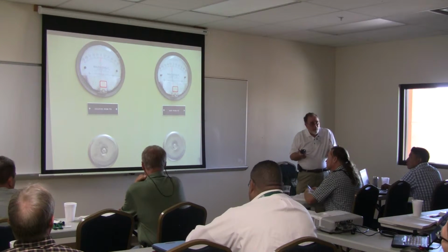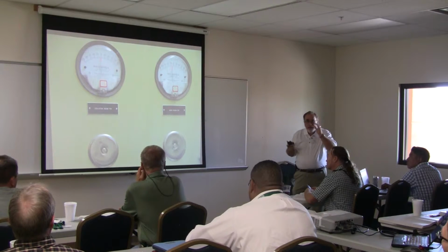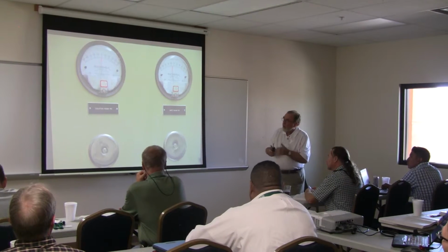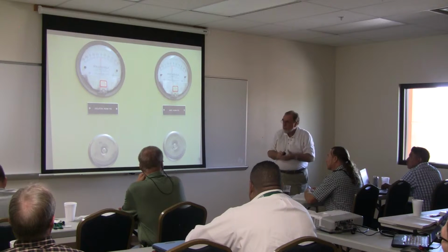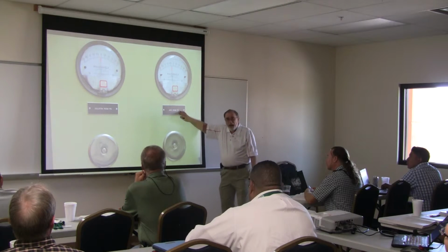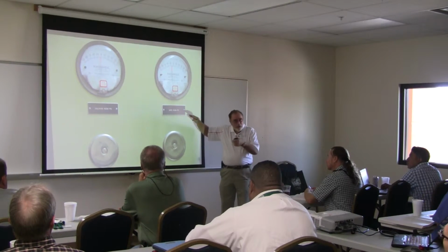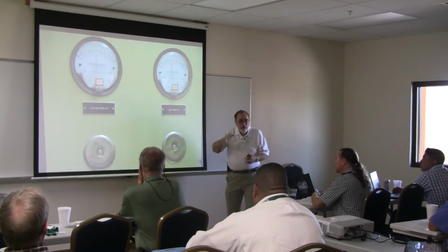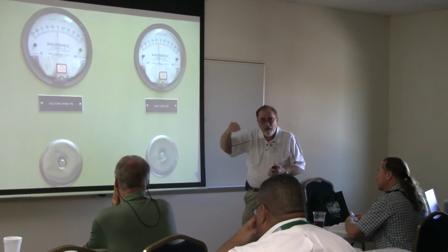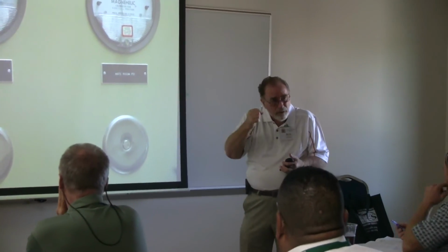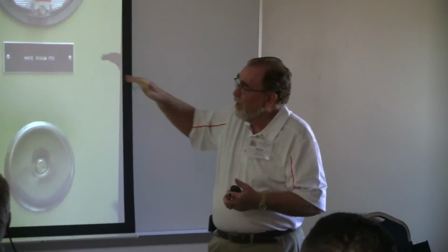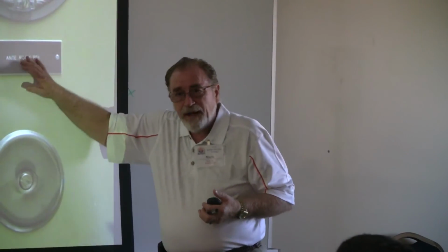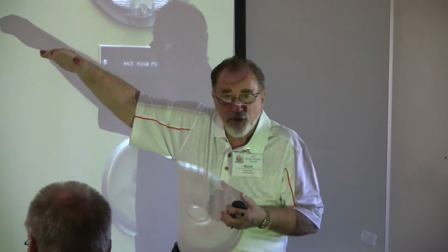Because you might have an airborne disease, all of the air is coming into the room. The anteroom is where people actually get dressed up to go into the isolation room. And again, the hallway is at a greater pressure from a mechanical system than the anteroom, and the anteroom is at a higher pressurization than the isolation room.